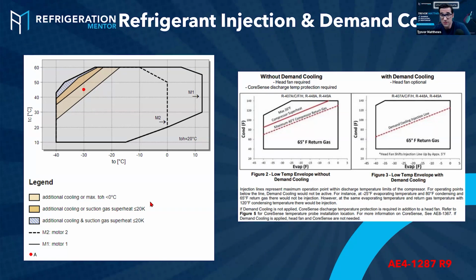The black lines, that's where the maximum the Bitzer compressor can run. Okay, same over here on this. Let me get the laser pointer up. This here is the operation envelope of a Copeland. Depending on the model number, it's going to change, so they're doing more of a rough idea. But this is a specific model number because I threw this into the Bitzer software, which I'll show you how to do. If I was running anywhere here, I do not need any additional cooling. Okay, don't need any additional cooling.